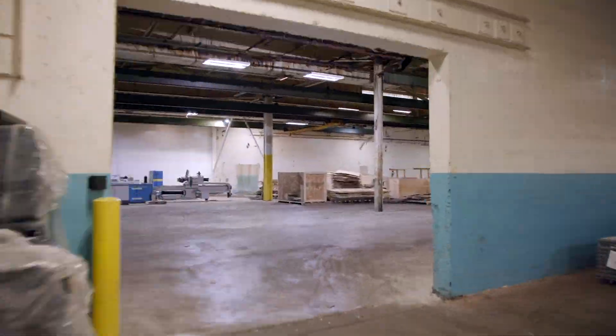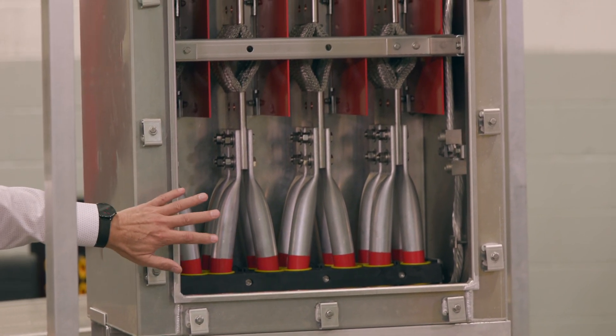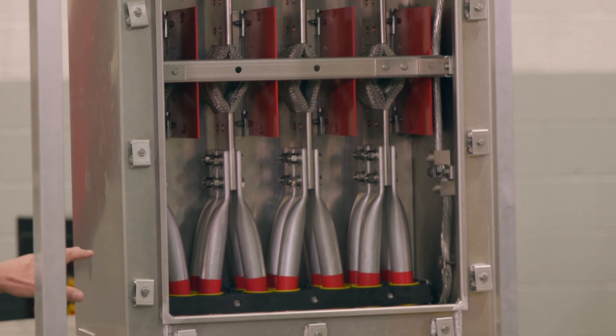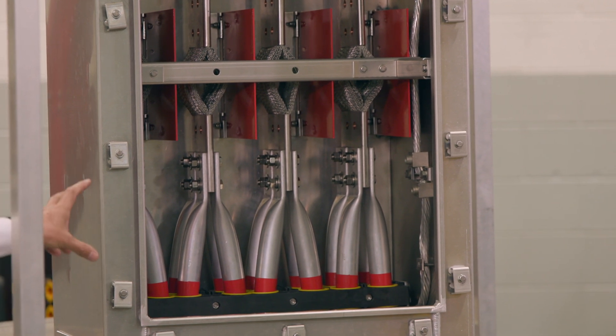It's the world's first wet-dry rated busway. This is designed to get wet — it's designed for water ingress, and when the water egress happens, it's still fully functional. It doesn't require powering down. It doesn't require maintenance. Once this plate is on and this enclosure is tight, you could essentially flood this floor and this Holobus will not be affected. It will not fail.